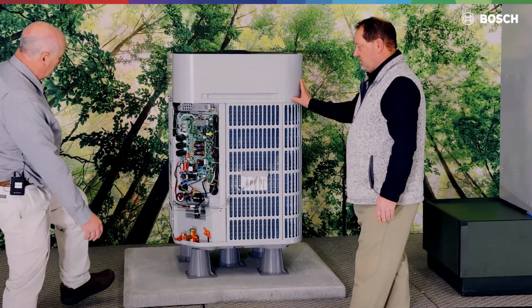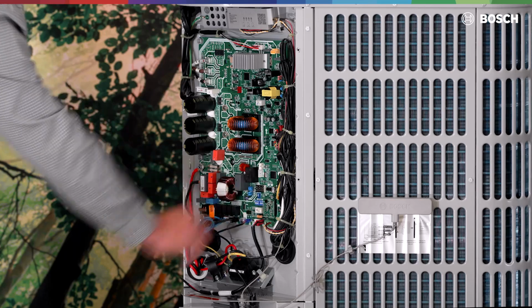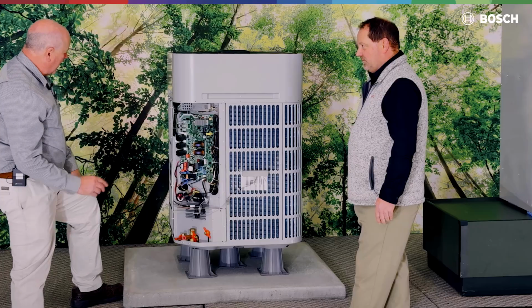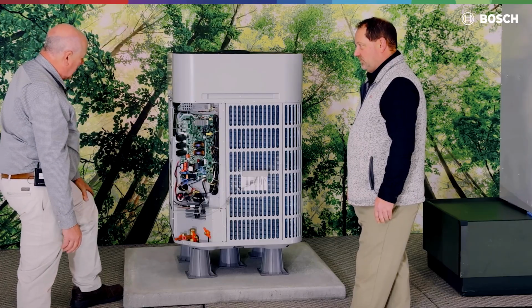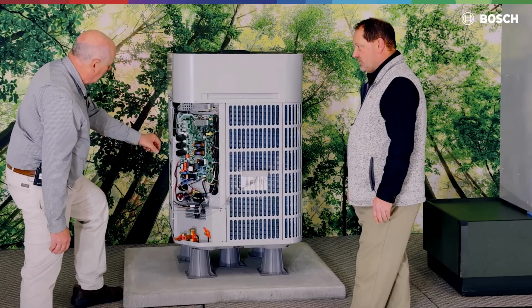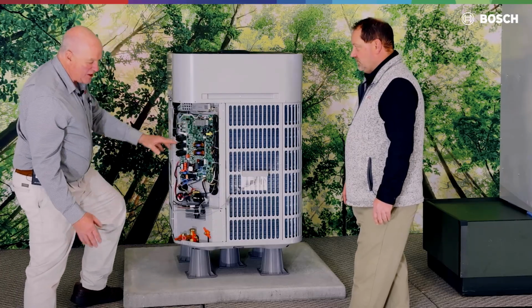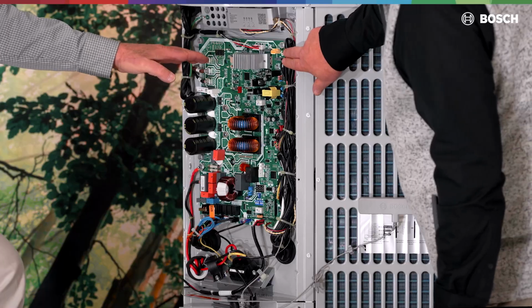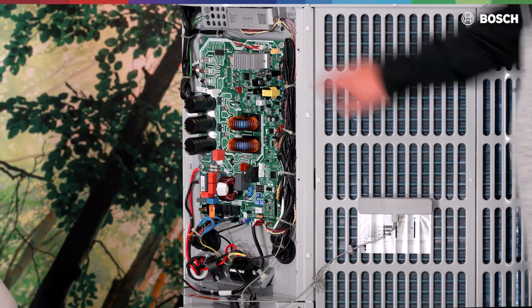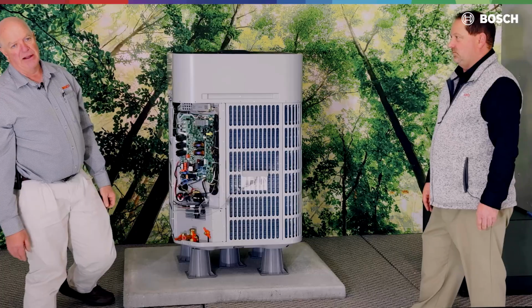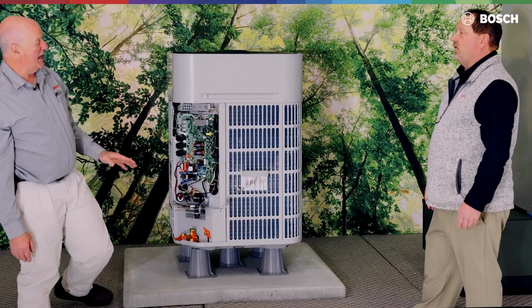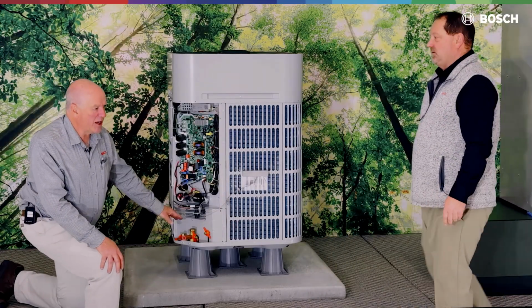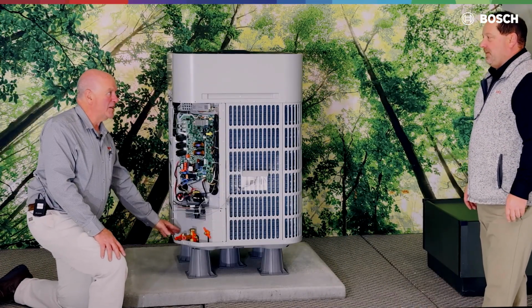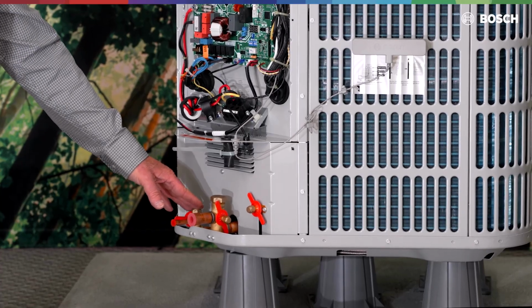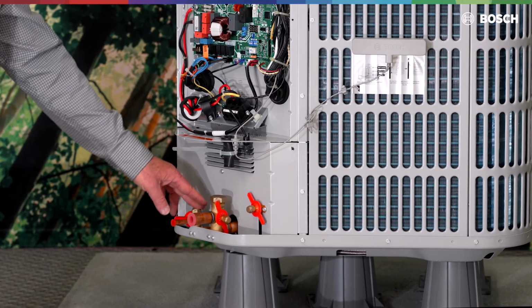So we've got our points down here that we can actually work with, our contacts down here to read that reading. That's important. We have our terminals P and N. P and N, we're on the board here to measure what is happening with that voltage. We've got to be at 42 volts or less on P and N before you put your fingers in that board. That is a safety concern again. Okay. So you always open up the suction valve first, then the liquid line second. That way we don't have oil dispersing out of the compressor section. So it's always suction line first.